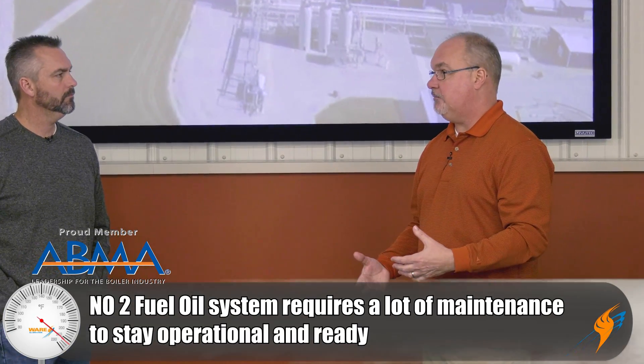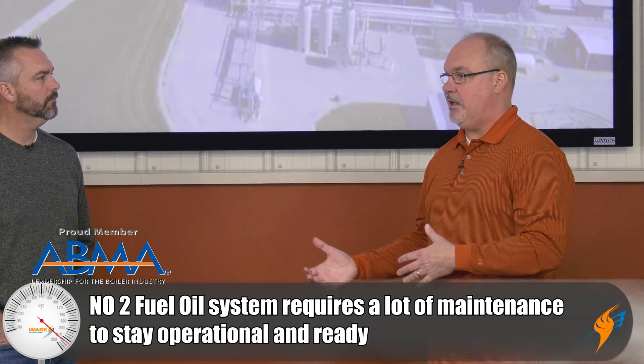Why would you do an LNG over, say, a number two fuel oil as a backup? In our experience, our number two fuel oil customers that actually have that as a backup — more often than not — they're not doing the things they need to do to keep the system operating and ready. Your number two oils, if you're not circulating properly and testing periodically, you'll end up cracking it, it'll water out, and it won't work when you need it. It can be a good backup, but it takes a lot more attention. With an LNG or even a propane, they tend to just take care of themselves, and when you need it, it's there.